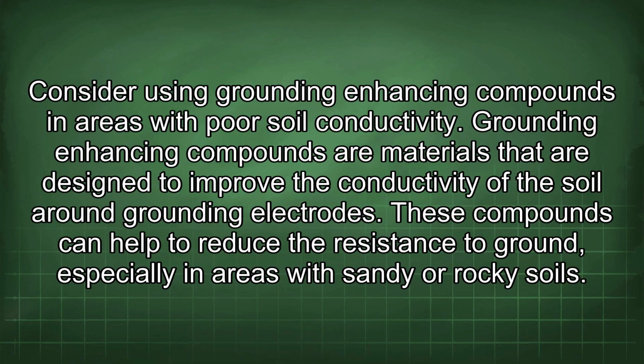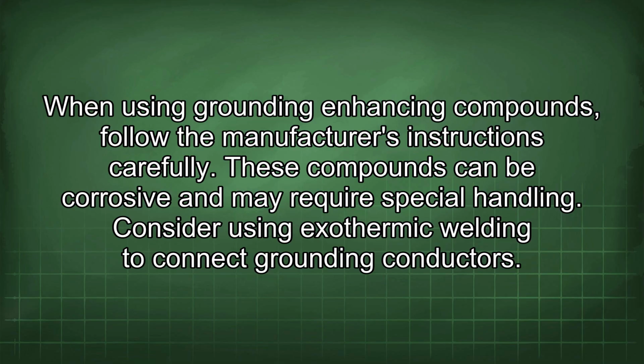Consider using grounding-enhancing compounds in areas with poor soil conductivity. Grounding-enhancing compounds are materials that are designed to improve the conductivity of the soil around grounding electrodes. These compounds can help to reduce the resistance to ground, especially in areas with sandy or rocky soils. When using grounding-enhancing compounds, follow the manufacturer's instructions carefully. These compounds can be corrosive and may require special handling.